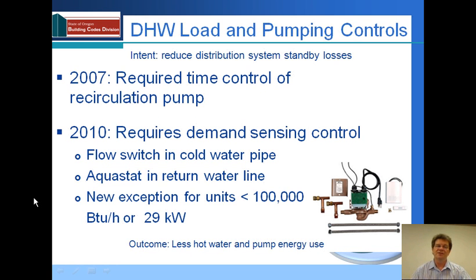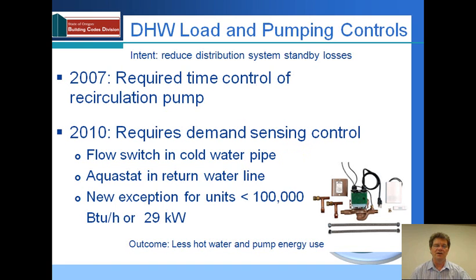The newer controls that are now available are required in the new code language. We look for a flow switch in the cold water pipe. This flow switch should basically turn that pump off unless we sense a demand for hot water. And then once that demand for hot water occurs, the pump will come on delivering water quickly to the person who needs it.